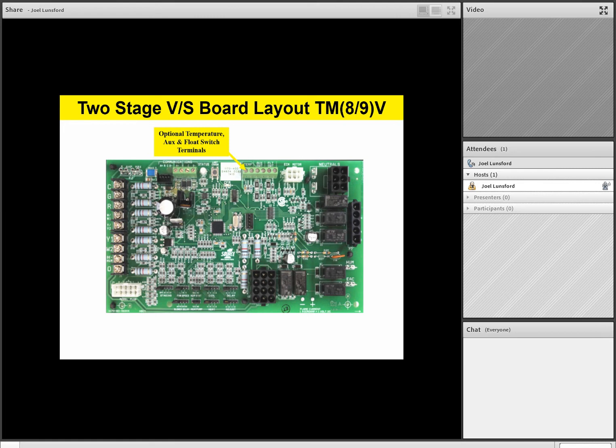Next to that is a 6-pin ECM motor plug. Now remember, team, like we said before, instead of having a physical jumper on the motor that we're going to move in the field, this ECM motor plug actually has some wires that go down to the variable speed motor, and then we're going to set up our airflow with some jumpers, which we'll talk about in just a little bit.